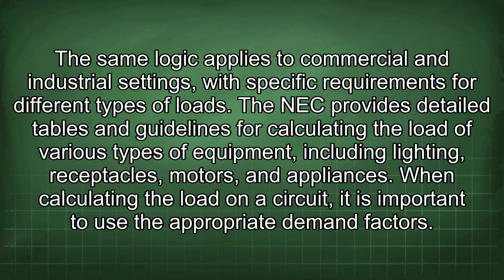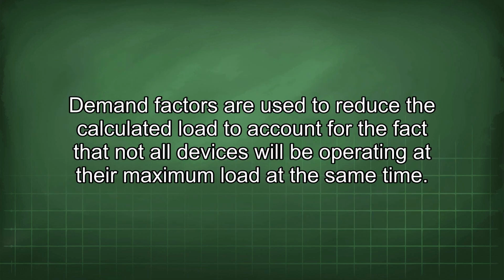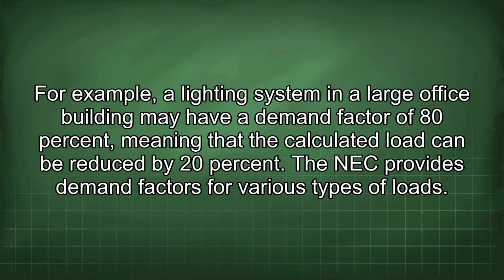The NEC provides detailed tables and guidelines for calculating the load of various types of equipment, including lighting, receptacles, motors, and appliances. When calculating the load on a circuit, it is important to use the appropriate demand factors. Demand factors are used to reduce the calculated load to account for the fact that not all devices will be operating at their maximum load at the same time. For example, a lighting system in a large office building may have a demand factor of 80%, meaning that the calculated load can be reduced by 20%.